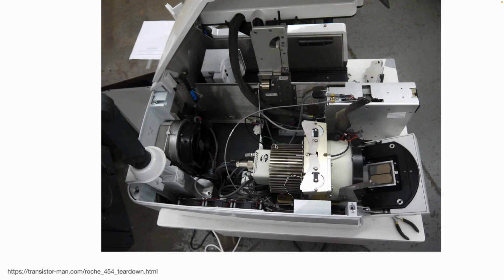The central camera here is this Spectral Instruments very fancy low noise camera, which is the bulk of what's going on, and it's directly coupled to the flow cell which sits here. This obviously makes the optical system much easier as well, because there's no objective focusing or filters. It's what's called a single channel instrument, so it's only imaging a single color, a single wavelength or set of wavelengths of light, whereas the other instruments are looking at different colors and having to use that filter wheel to split out the colors, right? This is a much simpler optical system.